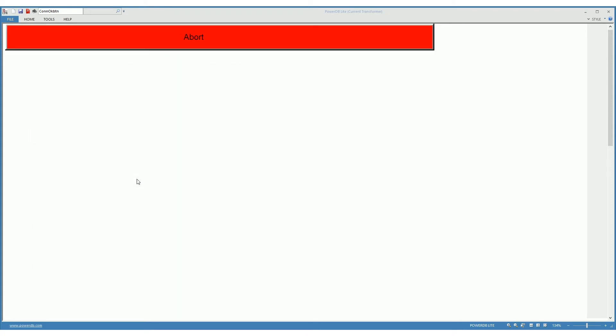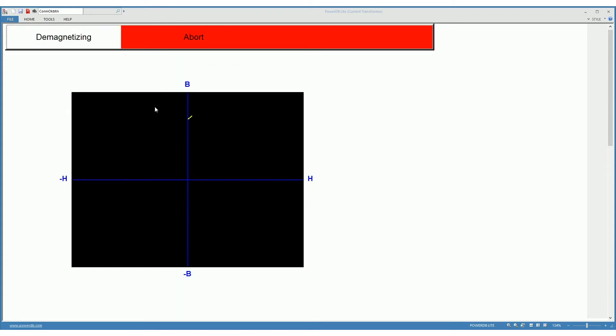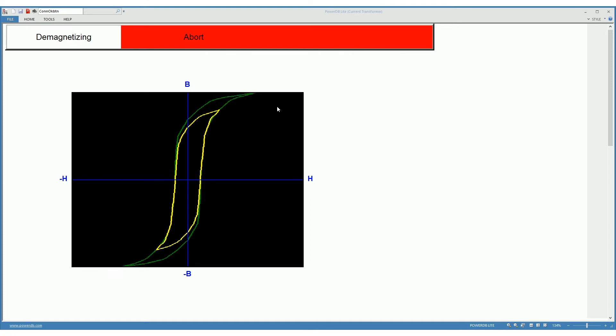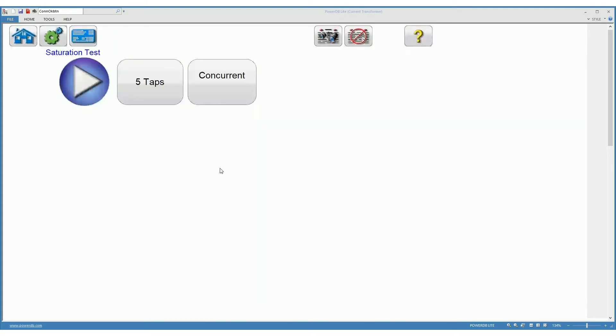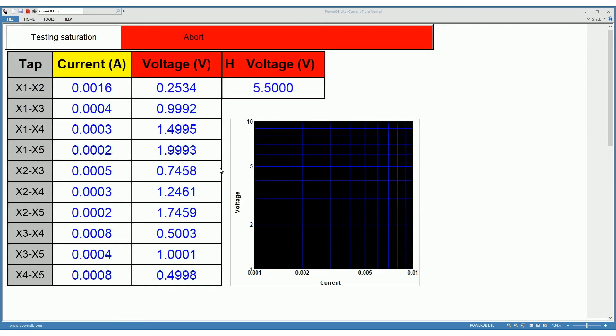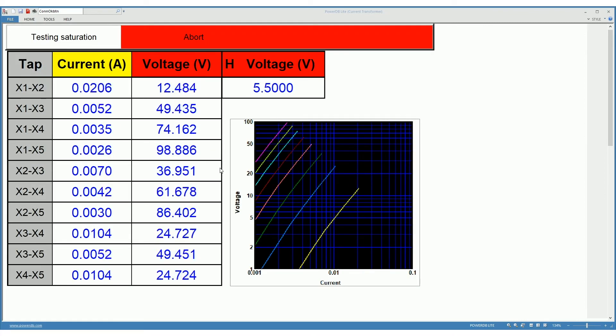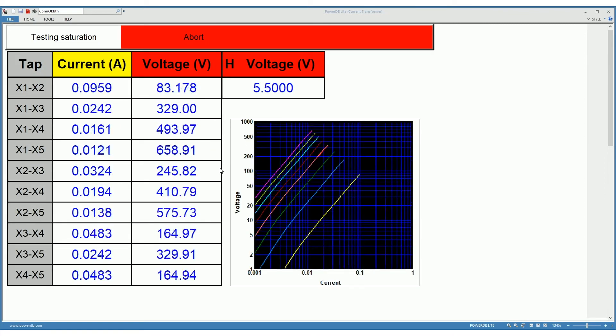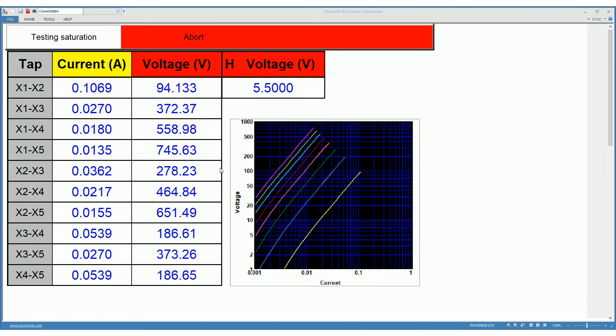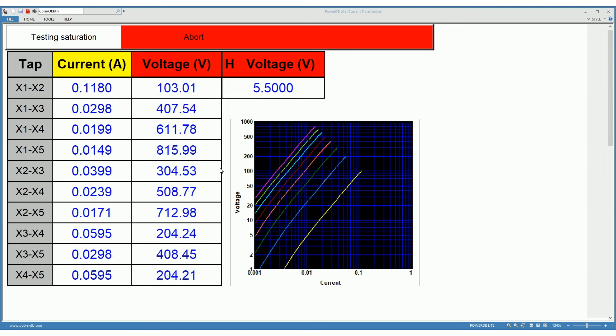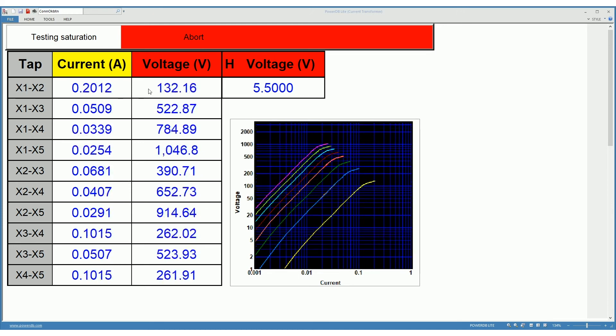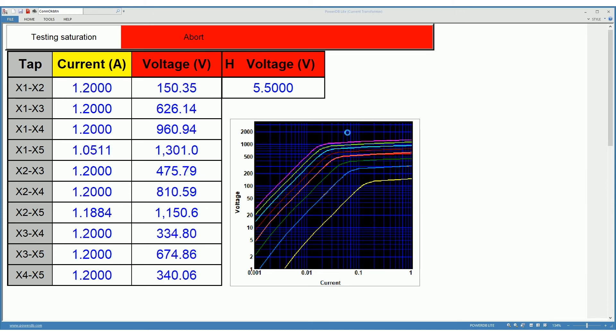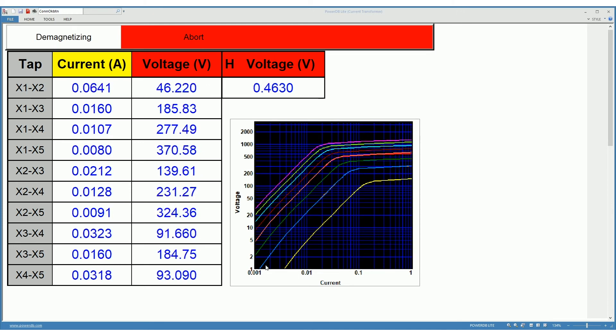After the winding resistance test, which is a DC test, we run a demagnetization procedure to make sure that we are in good shape for the saturation curve test which comes after this one. Here we are measuring the saturation curve of all the windings at the same time.